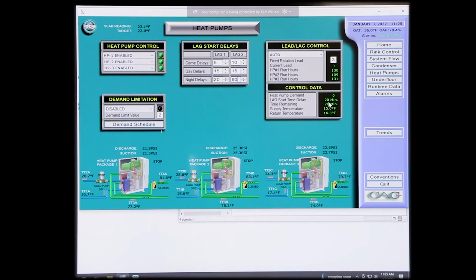Your lag start time, okay, 20 minutes. So it's always going to start the first machine that's in sequence to start first. Then the lag timer will kick in for the next machine to start, which is where you'll see time remaining. You'll see these two count down. Just a reread here again of supply and return temperature. Again, the starting and stopping of these compressors is based on that 10-degree max DT. We look at the return temperature of the glycol coming back based off the set point. So if we're looking at 20 degrees, we're looking for 10-degree return temperature. From that point below, that's where we start to back things off.